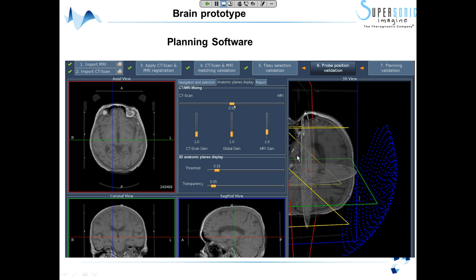And once this position has been selected, mostly perpendicular to the skull surface, then the software is computing the propagation of ultrasound between the target and the transducer, and the computation is achieved by using the CT data. Once the computation is done, we know what phase shift need to be applied, and here is an example of the refocusing that we can obtain. Here was an experiment on cadaver heads to test the accuracy of the system, and with dedicated MR images, we can measure the temperature elevation in the brain, and we compare the maximum temperature elevation on this image to the red point, to the actual target that was chosen.